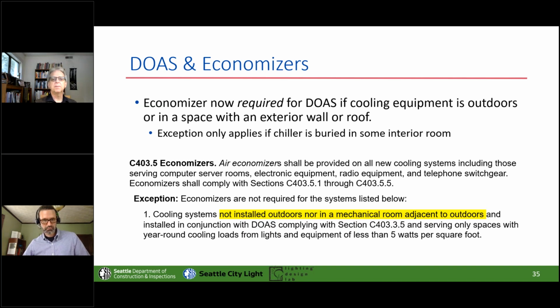DOAS. So if you've got DOAS, you need economizer anyway, if your chiller or heat pump is outdoors, or if it's in a space that has a wall or a roof adjacent to the outdoors. If your only mechanical space is deep inside the building someplace, obviously getting that quantity of air in and out would be too much of a burden. But if you're next to a wall or a roof in your mechanical room, do a louver and start hauling air in.